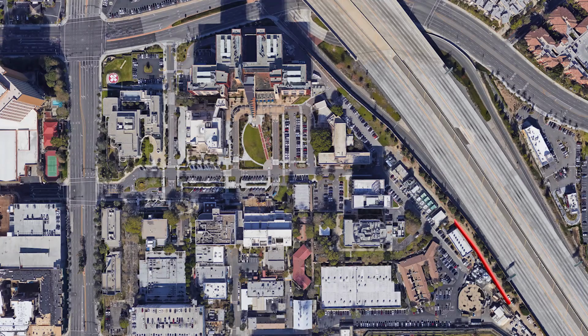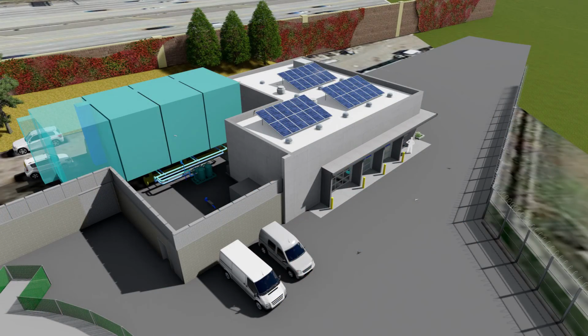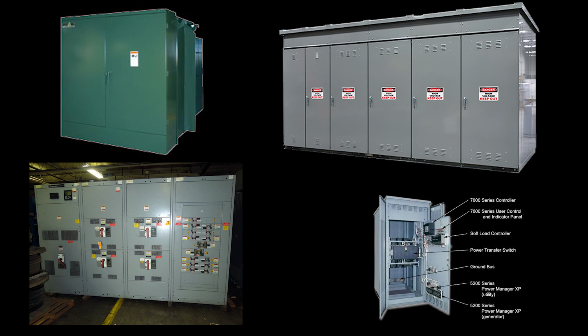New 18-inch chilled water piping mains from this new central plant will connect to the existing 12-inch chilled water piping currently serving the Douglas Hospital and will continue as a new 14-inch chilled water piping to connect existing buildings 1A, 3, and the future emergency department expansion building. The central plant will also have 3 new cooling towers with a provision for a 4th tower to support the proposed 3 chillers and future 1,000-ton chiller. New 12 kV normal and emergency transformers, 480-volt switchboards with a new transfer switch will be provided to meet the power demands of the proposed central plant.